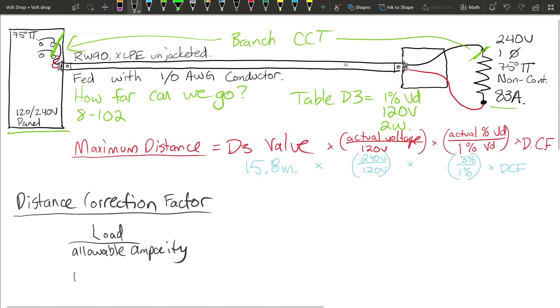Now we need to determine which temperature column to use in Table 2. Rule 4006(1) tells us that if we have a termination temperature listed — 75 degrees here — even though we have 90 degree insulation, we go with the lowest termination temperature. So we use Table 2 in the 75 degree column to pull the allowable ampacity of the conductor.